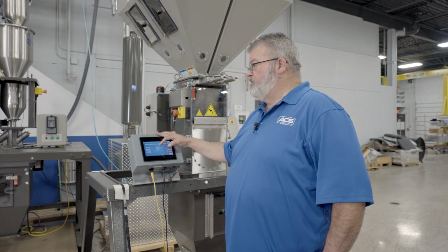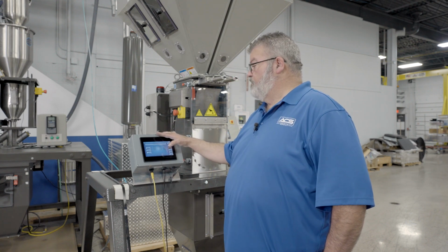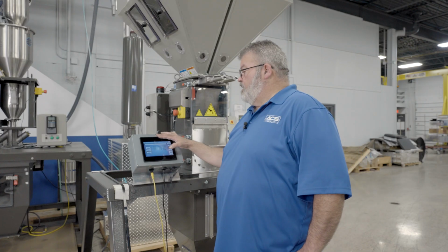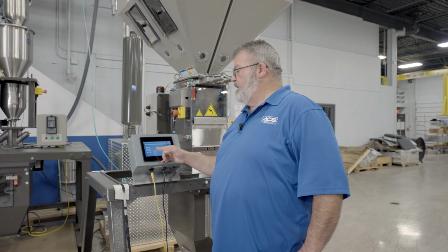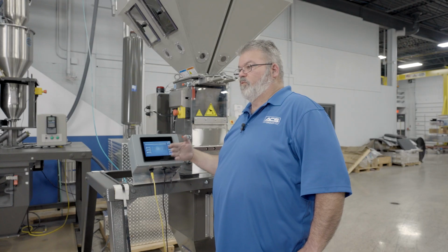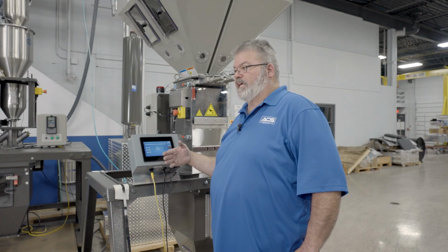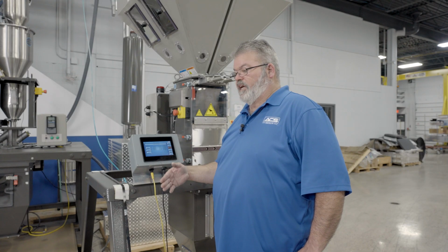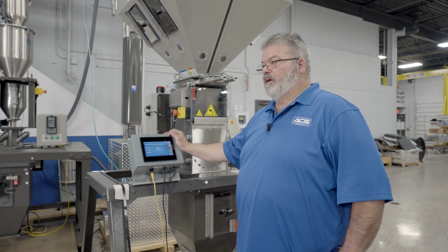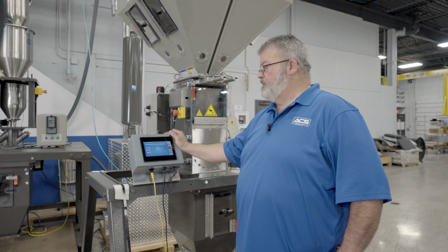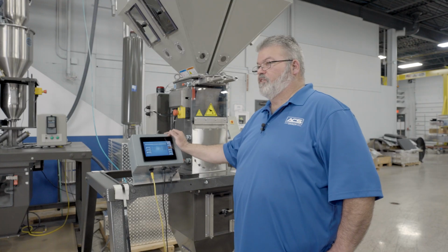If you turn the alarm off and you run out of material, you'll never get an alarm. The only real reason you'd ever want to set your alarm to no retry is if you're running a regrind that's not consistent, so you're doing grinding beside your press, feeding straight back into the blender, and that regrind won't always be present, you may want to change your alarm to no retry.